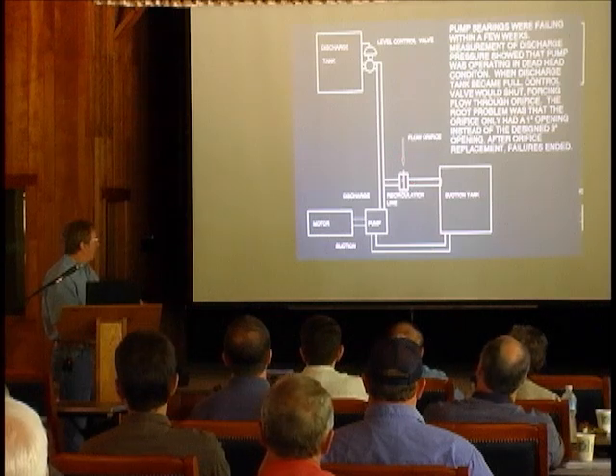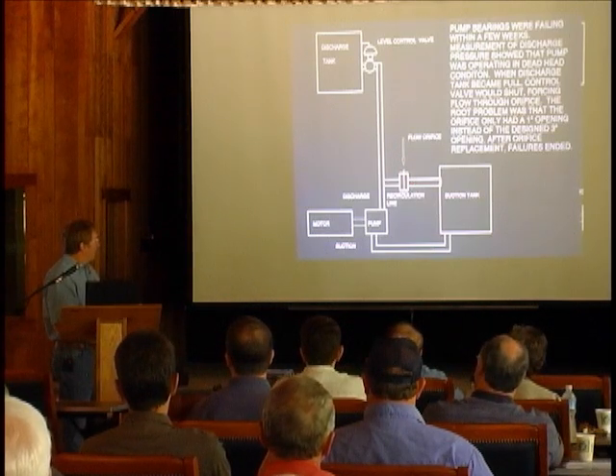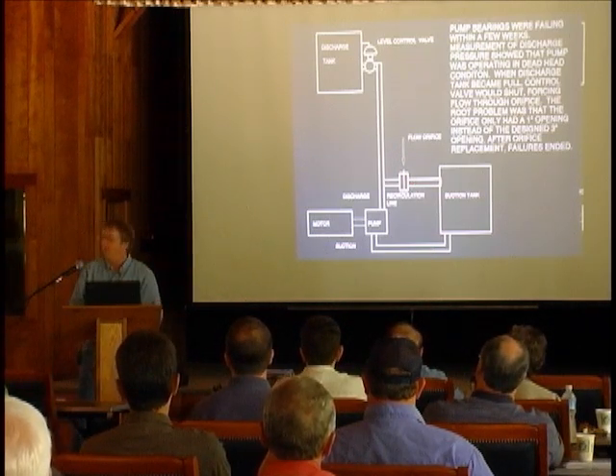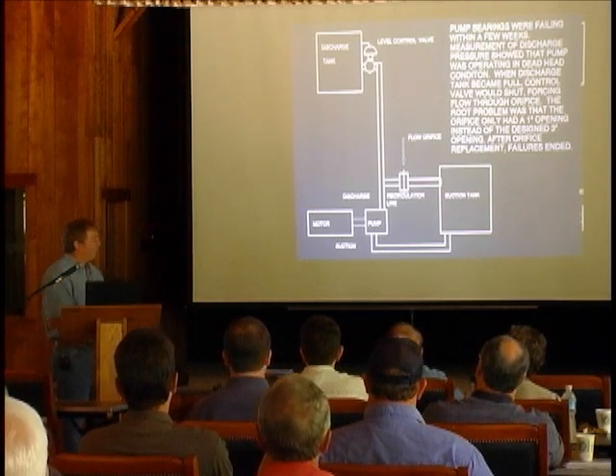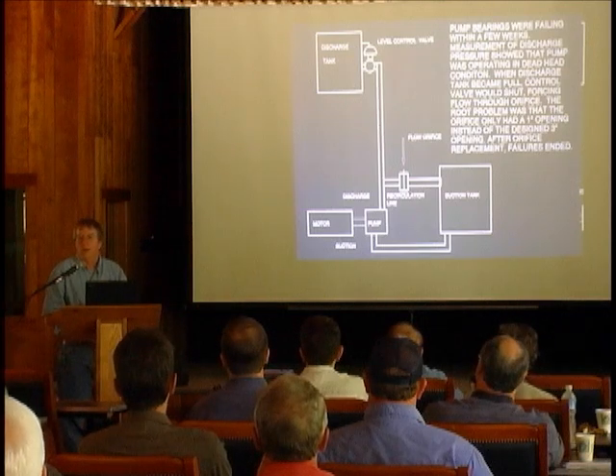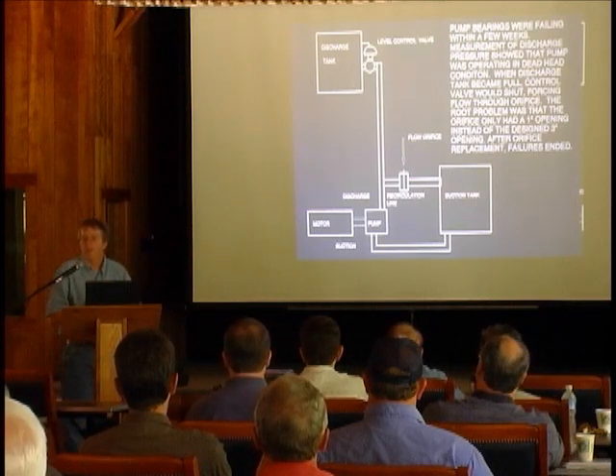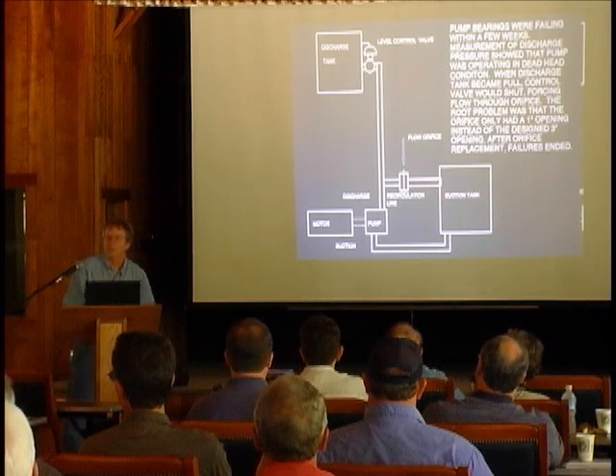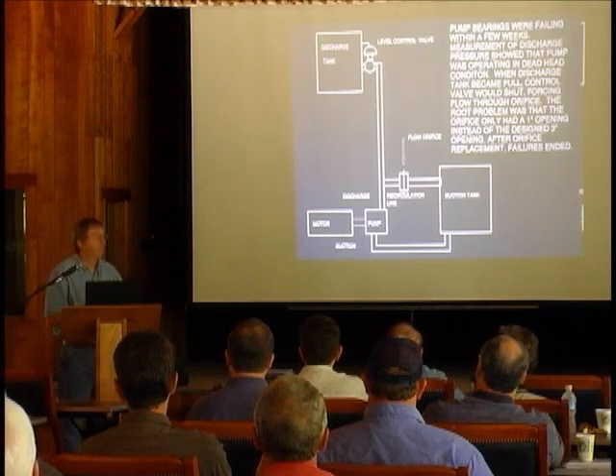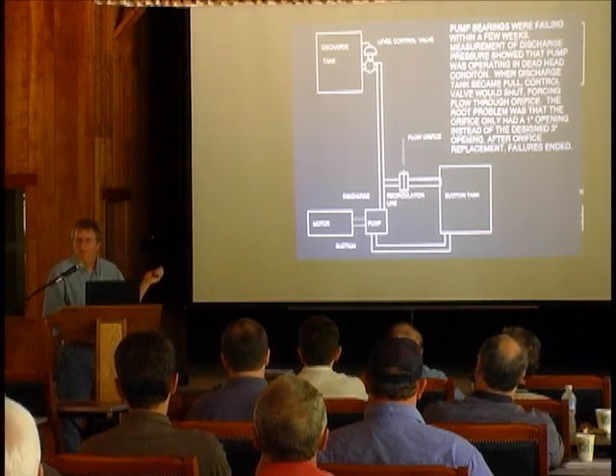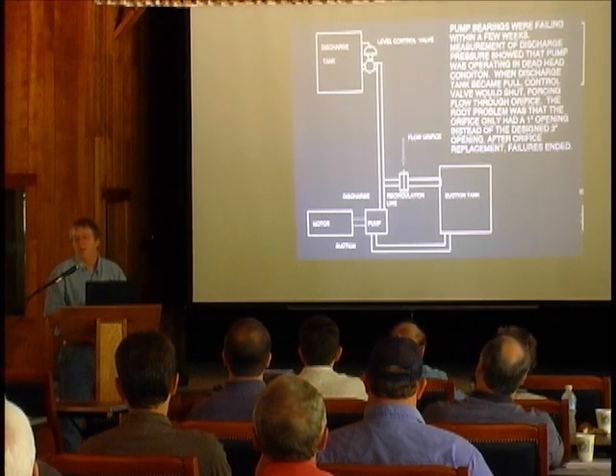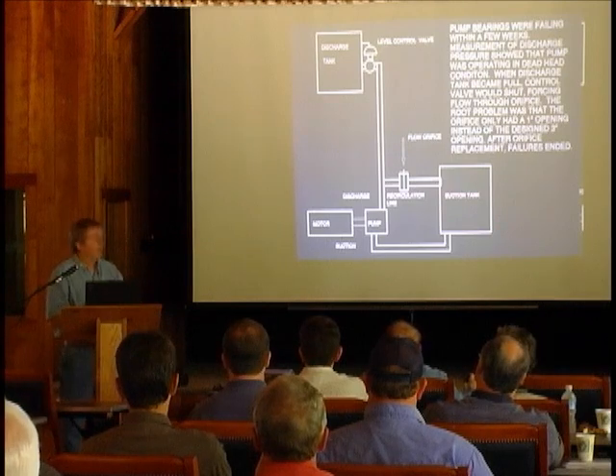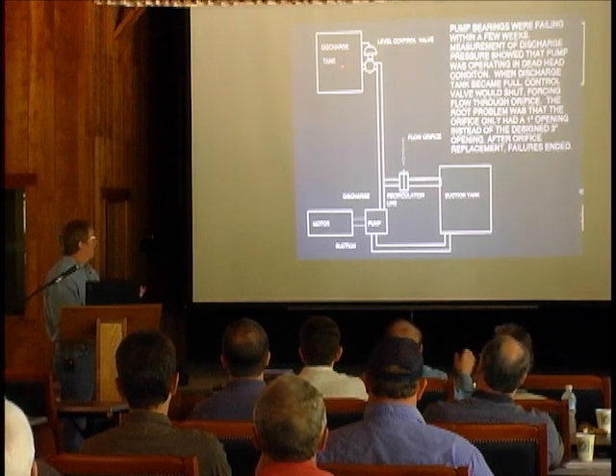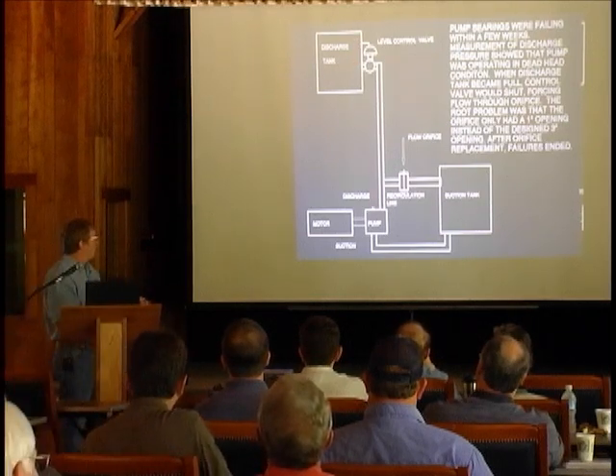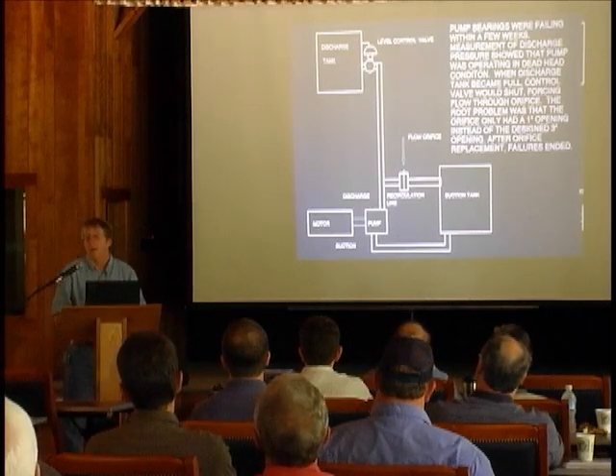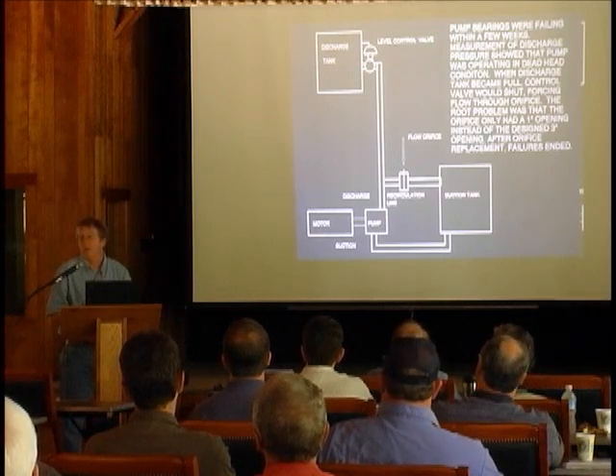So they had a flow orifice there, and I looked at it, and they have a little tab, and it said 2.000, meaning it had a 2-inch hole in it. And I said, well, wow, this is supposed to have a 3-inch hole in the orifice. So pi r squared, that's a lot of difference, 9 to 4. Took it out, and it had a 1-inch hole in it. So instead of a 3-inch hole in the orifice, it had a 1-inch hole. Basically, whenever this tank got full, this pump was just sitting deadheaded, and that would cause axial shuttling, and that would tear out your bearings.